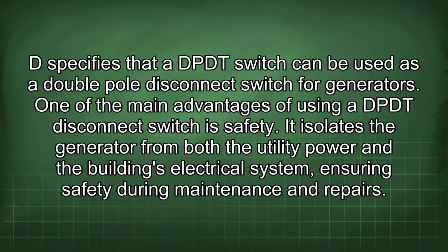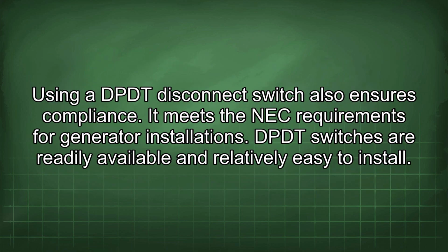One of the main advantages of using a DPDT disconnect switch is safety. It isolates the generator from both the utility power and the building's electrical system, ensuring safety during maintenance and repairs. Using a DPDT disconnect switch also ensures compliance. It meets the NEC requirements for generator installations. DPDT switches are readily available and relatively easy to install.